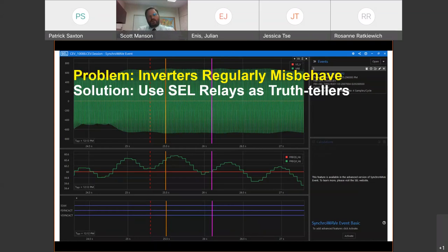And there was a job site where multiple DERs were misbehaving. And there was a lot of finger pointing and the integration wasn't going well. And as usual, the answer came out of the relay. The relay will be a truth teller. It will tell you who's the true culprit in the room, who's causing this frequency oscillation, and we found it very quickly. You just have to use the data recording in it that's been in the relay since the 1980s. Turn on a feature, use a feature that's been there for 30 and 40 years in some cases.